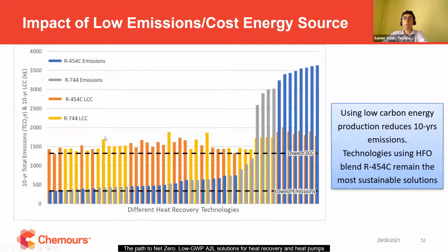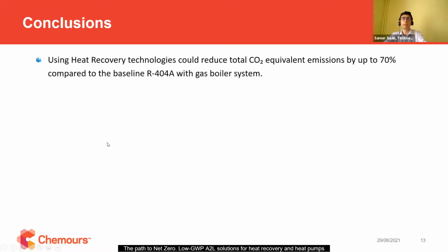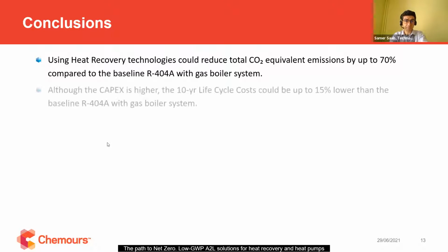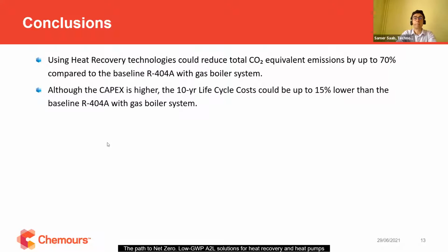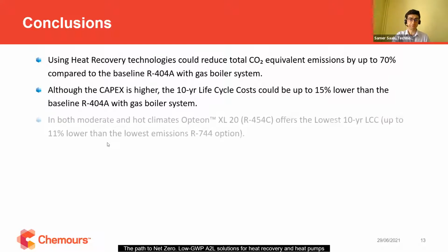So XL20, in conclusion, today is a good technology to perform heat recovery while reducing emissions up to 70% compared to a 404 system using a gas boiler. Even though CapEx might seem higher at first, the life cycle cost would be reduced by down to 15% compared to technologies using 404 with a gas boiler.